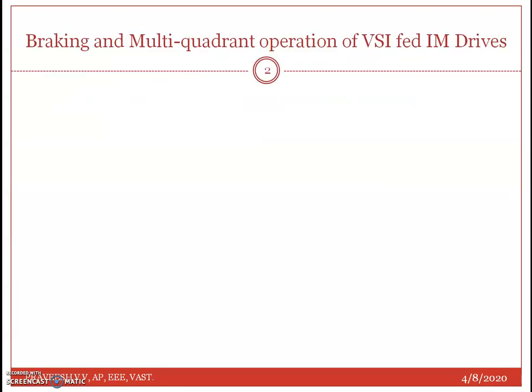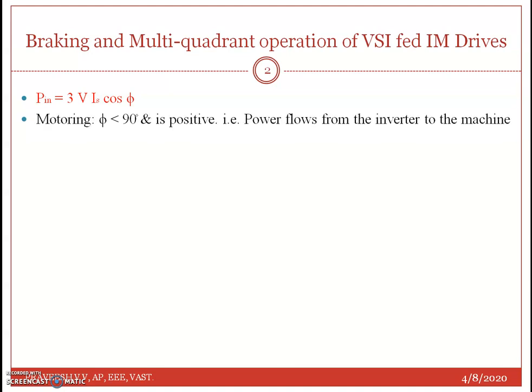Now we will be discussing more about the braking and multi-quadrant operation of VSI drives, and also closed loop speed control. The power input is given by 3·V·Is·cos(φ), where V is the fundamental component of the motor phase voltage, Is is the fundamental component of the motor phase current, and φ is the phase angle between V and Is. For motoring operation, φ will be less than 90 degrees and power flows from the inverter to the machine.